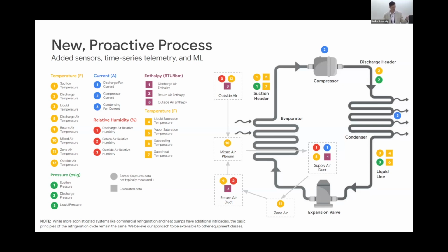And we kind of focused on the suction header, discharge header, the liquid line, and we put pressure and temperature taps into those things. We actually physically instrumented those. And that is kind of a challenge to scale this wide, on a large scale. That's the biggest challenge, is inserting these pressure and temperature sensors into the refrigerant line.